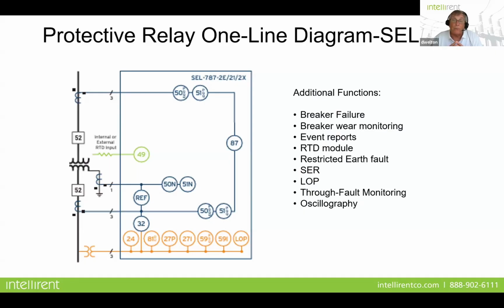Loss of potential. If you have a VT fuse loss, your voltage elements will become disabled, so it won't nuisance trip, but it will close an alarm. Through fault monitoring is one of the things that's very much overlooked when people set protective relays for transformers, and then oscillography. So I'll tell you a little story.